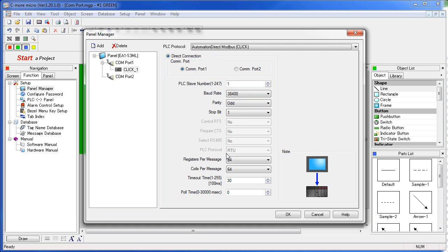Just double-check that the parameters match those of the PLC project you're connecting to. Make sure that the PLC slave number matches that of your PLC project, otherwise the panel won't talk to your PLC.